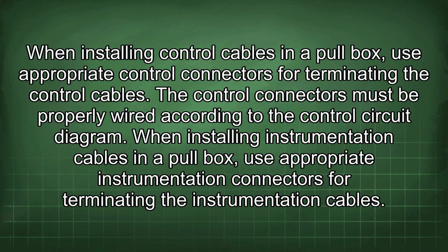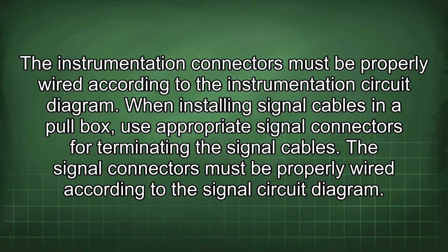When installing control cables in a pull box, use appropriate control connectors for terminating the control cables. The control connectors must be properly wired according to the control circuit diagram. When installing instrumentation cables in a pull box, use appropriate instrumentation connectors for terminating the instrumentation cables. The instrumentation connectors must be properly wired according to the instrumentation circuit diagram.